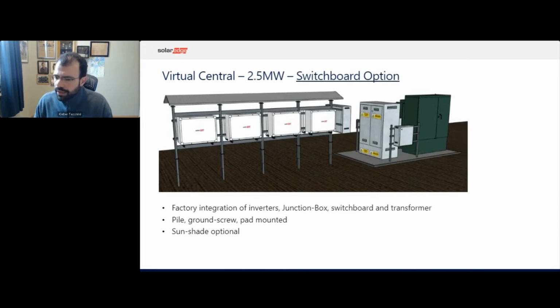Second design is a 2.5 megawatt AC. The design includes an inverter rack with 8 inverters, a junction box between the inverters and the AC switchboard, plus auxiliary components. That junction box is there so that everything is wired to the junction box from the inverter on the AC side, and then from the junction box in the field, you can wire to the switchboard. The AC switchboard with inverter breakers and optional main breaker can be mounted on a platform on a pad, close coupled with the transformer. And information on Virtual Central designs will be available during the sales process, and our sales and application engineering team will be happy to support you to tailor this solution to your project.